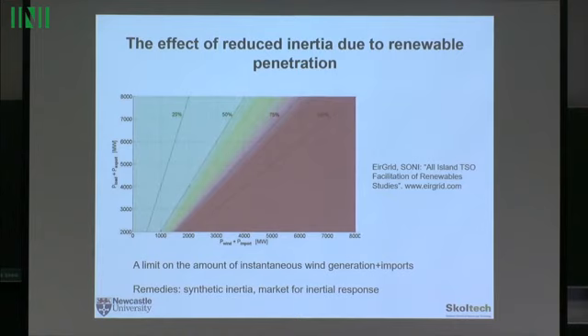The problem with low inertia is technical, so there are technical fixes. For example, there's synthetic inertia. A lot of wind is connected, and one way to increase this penetration is forcing wind generators to participate in frequency control. Initially they didn't participate, but now they're forced by regulation in Ireland to do so.